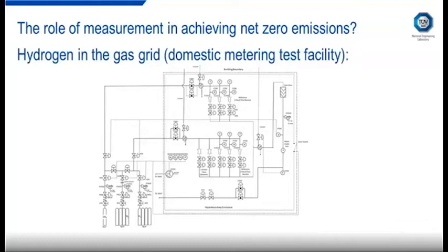It looks quite complicated, but that's just because we have 2 different inlet streams for the mixtures. The general principle is quite simple. We have a pressurized gas supply, and we blow down to atmosphere. We have individual reference meters, then we have the combined streams which are mixed before the test section where the meter is installed, the test meter.